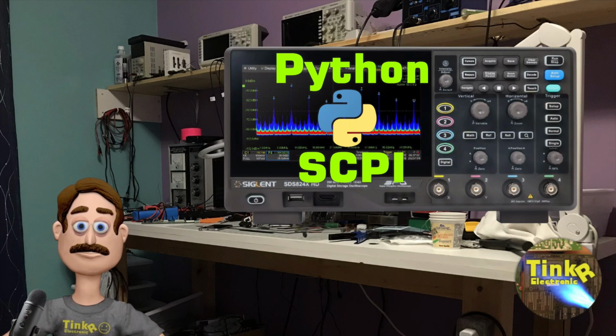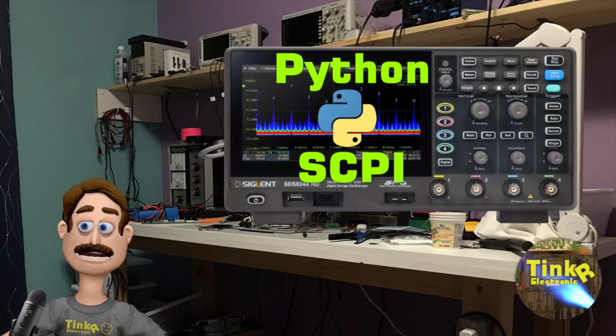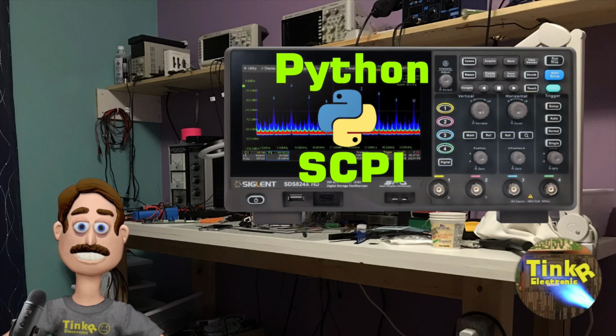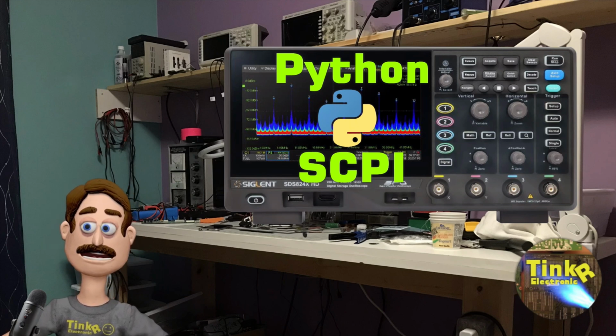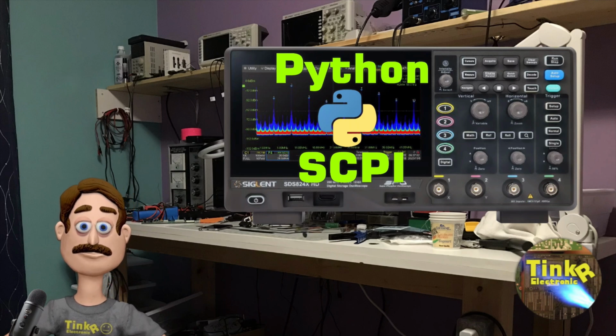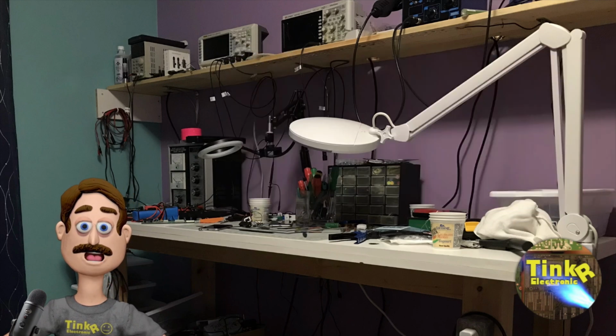SCPI stands for Standard Commands for Programmable Instruments. What that means is there's a vast array of laboratory equipment that can be controlled via commands like this. This SDS804X HD is one of them, but my Keysight behind me is also able to be controlled via that same command interface. Now it may be over LAN, RS-232, or USB. So I'll bring up a fresh install of Windows so we can see how to do this.